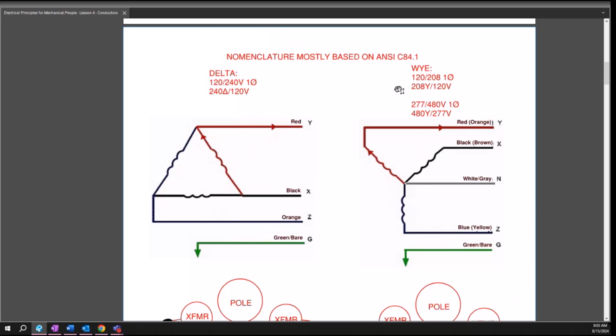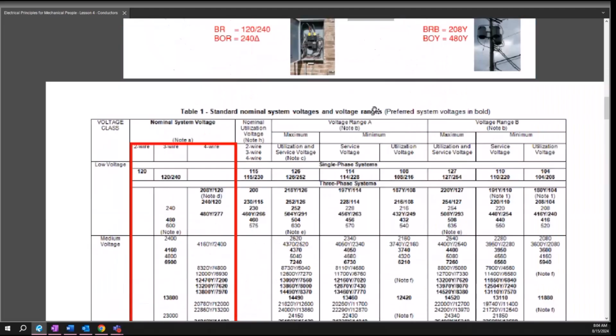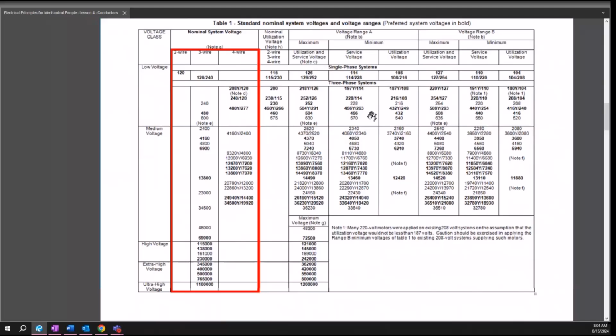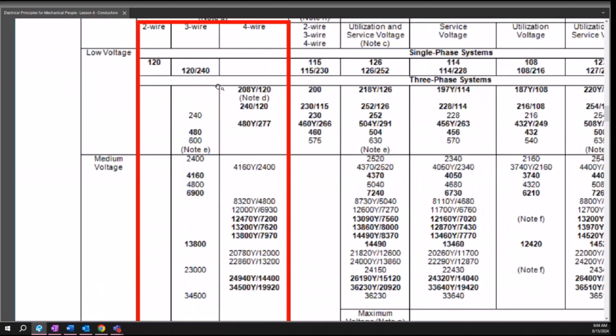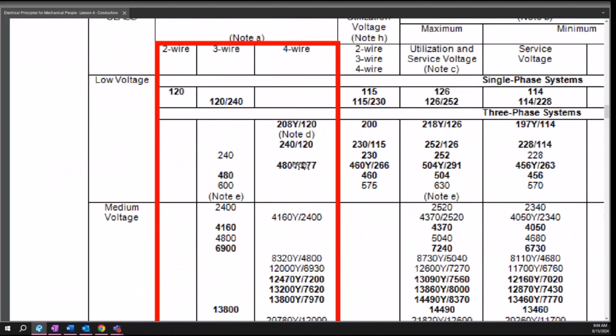The nomenclature I've shown here is based mostly on the ANSI C84.1 standard. This table comes out of that standard, and you can see where I got that nomenclature. They're not using the delta symbol, I don't know, maybe whenever they typed this up they didn't have the symbol, so I add it in because it's a lot simpler. You can see 3-wire single phase, so this is single phase voltage here and here, whereas this is 4-wire, which means it's 3-phase.